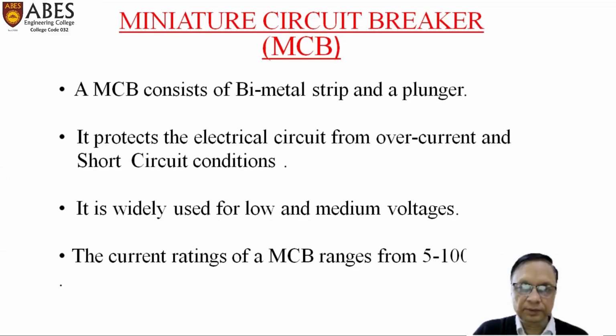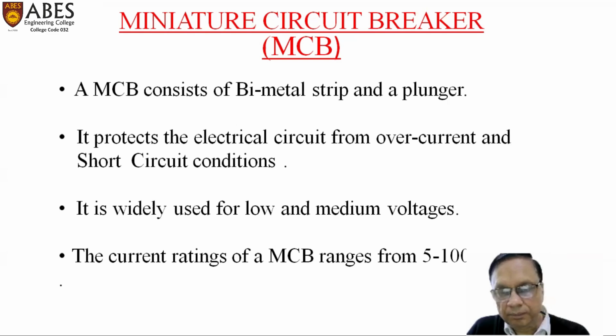So there is a difference between overcurrent and short circuit. Short circuit is an instant fault. In this case, the current reaches a very high value instantly, due to which the breaker will trip immediately. So we should not confuse overcurrent and short circuit conditions. Now it is widely used for low and medium voltages. We have seen it in many places. Maybe single phase, maybe three phase, but an MCB only works under the overcurrent principle and the short circuit condition. The current rating of an MCB usually ranges from 5 to 100 amperes. So it is used only for very low capacities.